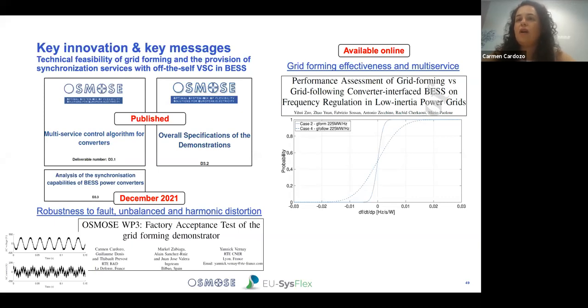the fact that when you have a really fast frequency response with a grid following, or when you have grid forming behavior, you see in equivalent tests, this is a real-time simulation, quite a difference in the shape of the RoCoF. So I invite you to check this paper, where the idea was to discriminate a grid forming from a grid following from measurements of the service provided to the grid. So we could prove that we can measure the effectiveness of the service provided by the grid forming capability.